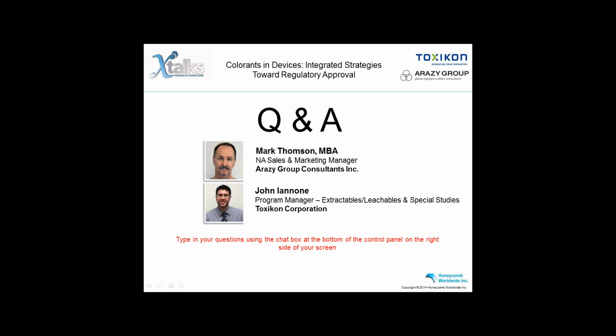Extractability is whether or not we can pull that compound out under more aggressive conditions for identification purposes, but not necessarily look at that as the total amount that will be delivered to the patient, which is then related to leachability and bioavailability. So it's really important, and this is why it's such a great question, to understand all three of these mechanisms and how they come together. But yes, they are all slightly different. I would say it has a lot to do with what aspect you're looking at: leachability from the device under clinical use, or bioavailability to the patient in terms of toxicological evaluation. And of course, extractability in order to better define what you have to start worrying about in the first place.